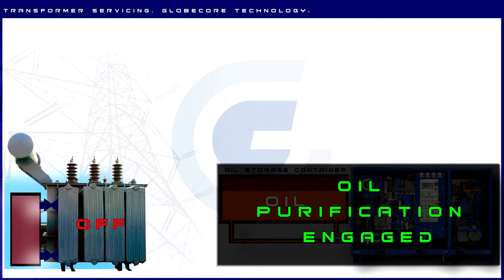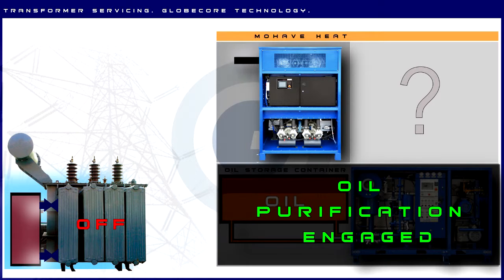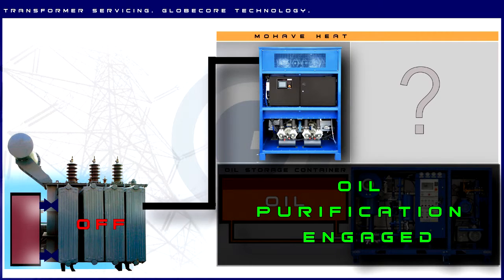While the oil is being purified, we connect the GlobeCore Mohave Heat unit to the transformer to protect its windings from moisture while the transformer is not airtight. Mohave Heat creates excess pressure in the transformer tank, preventing moist atmospheric air from entering. The Mohave Heat unit is engaged and the transformer tank is purged with dry hot air.